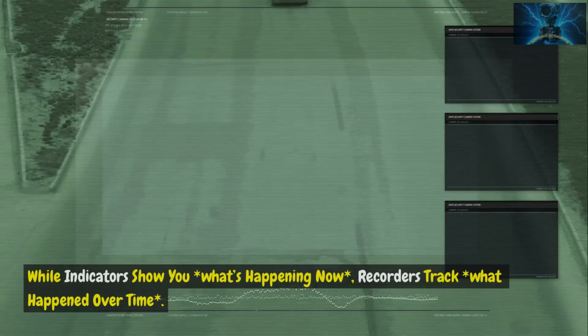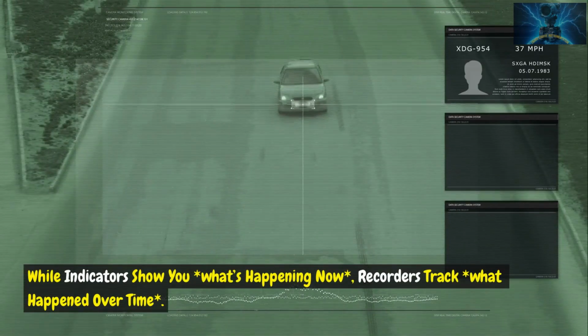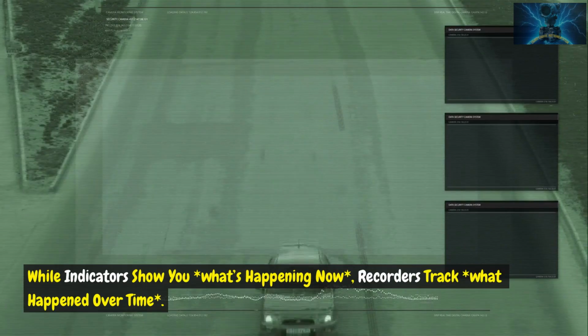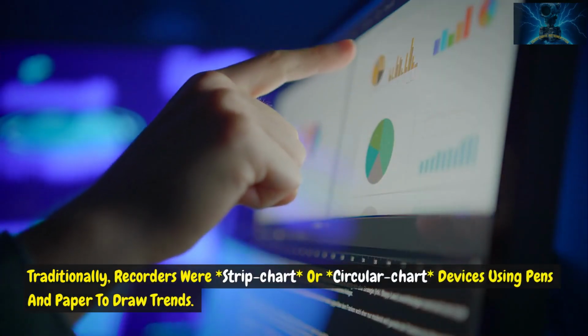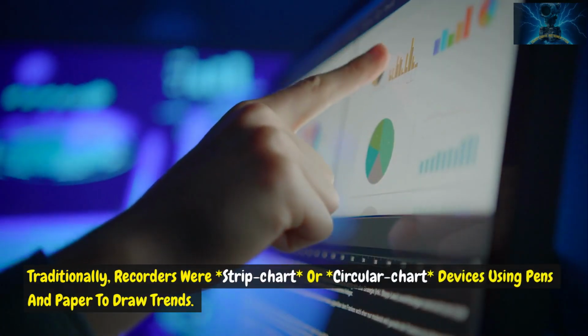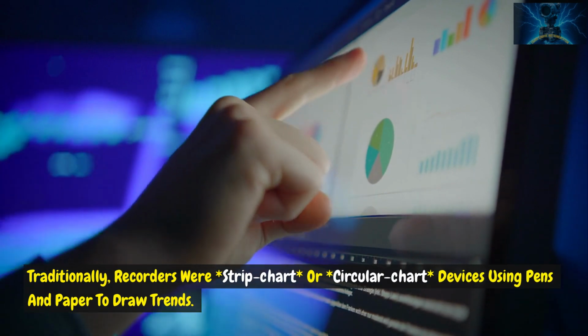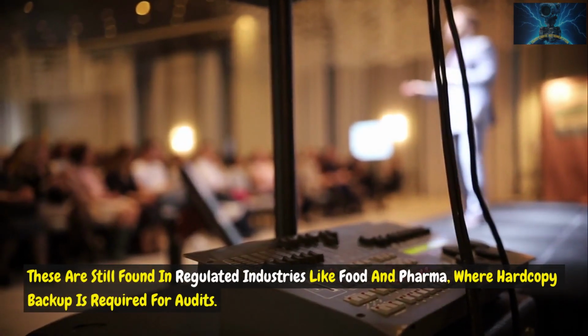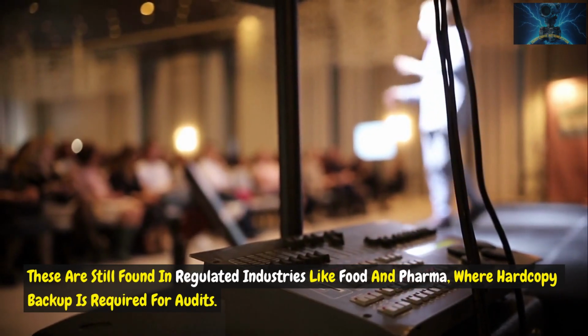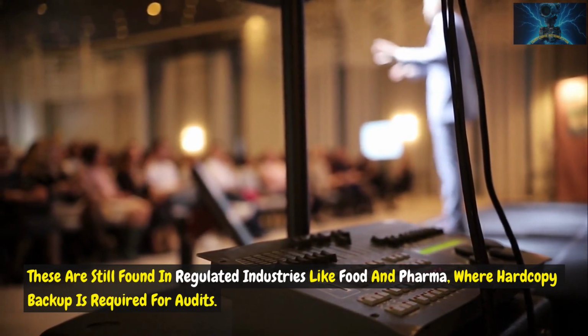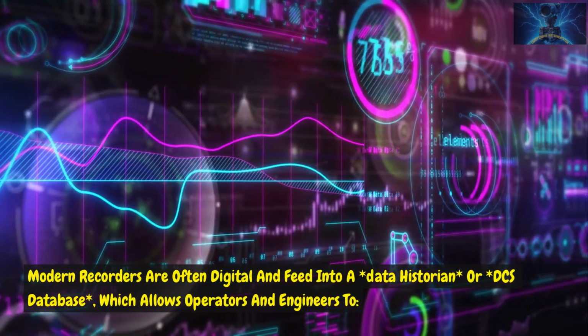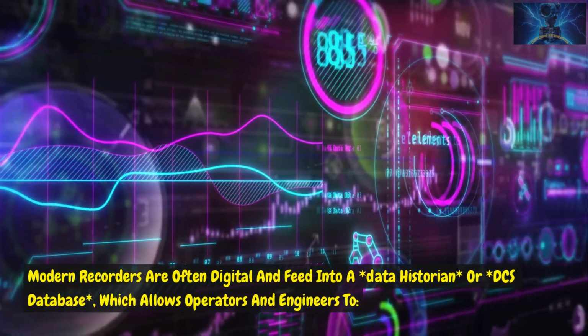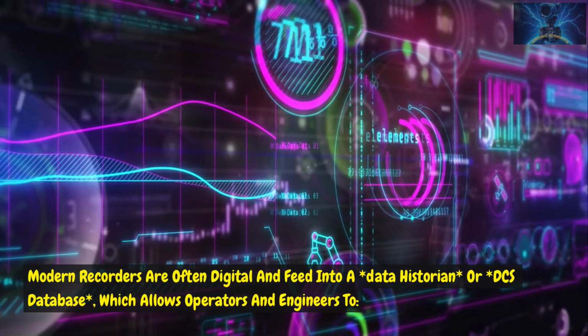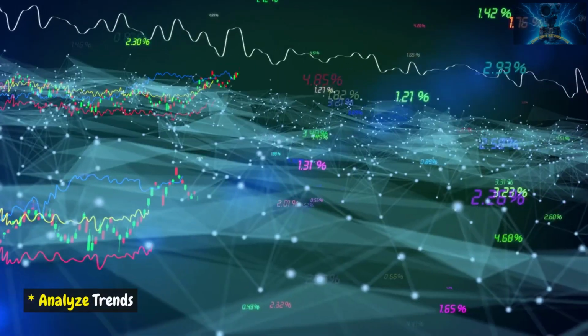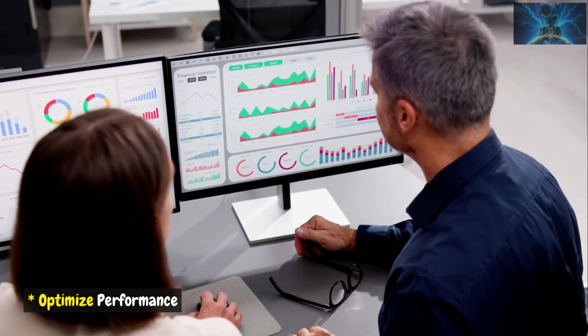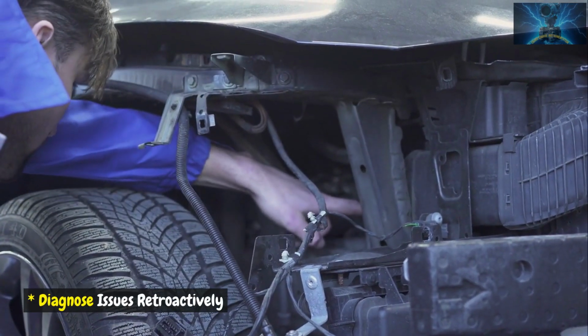Recorders. While indicators show you what's happening now, recorders track what happened over time. Traditionally, recorders were strip chart or circular chart devices using pens and paper to draw trends. These are still found in regulated industries like food and pharma, where hard copy backup is required for audits. Modern recorders are often digital and feed into a data historian or DCS database, which allows operators and engineers to analyze trends, optimize performance, and diagnose issues retroactively.